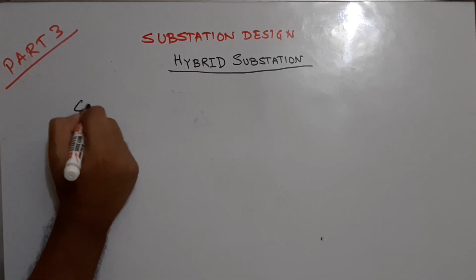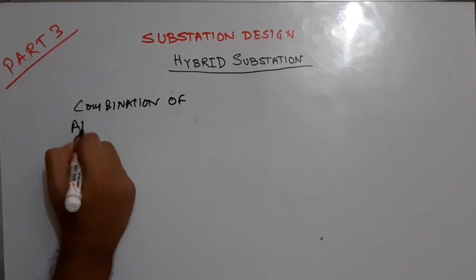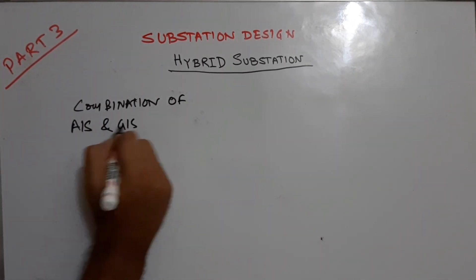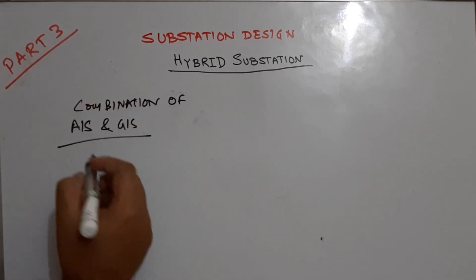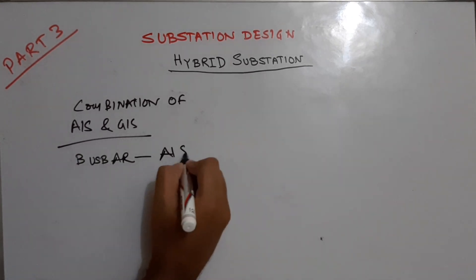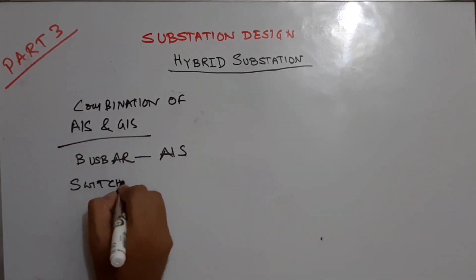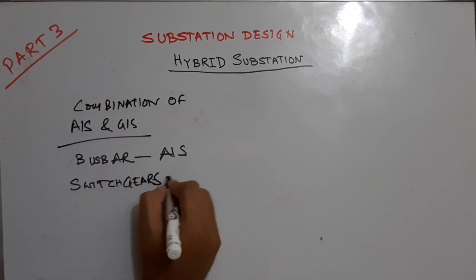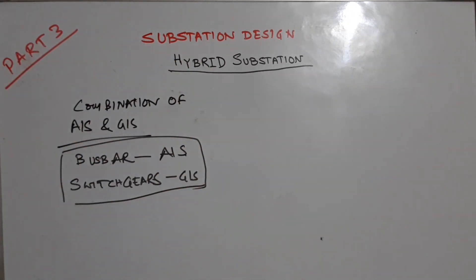In a hybrid substation, the bus bar arrangement is AIS — air insulated — and the switchgear arrangement is GIS — gas insulated. So the combination of an air insulated bus bar with gas insulated switchgear is what forms a hybrid substation.